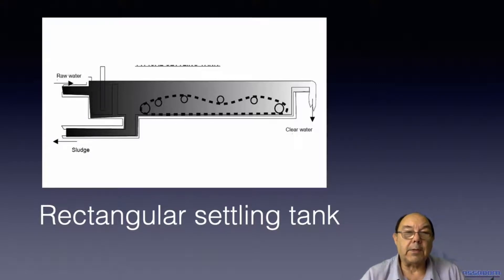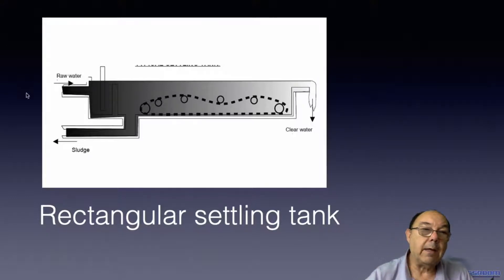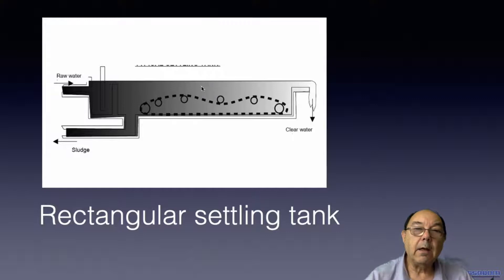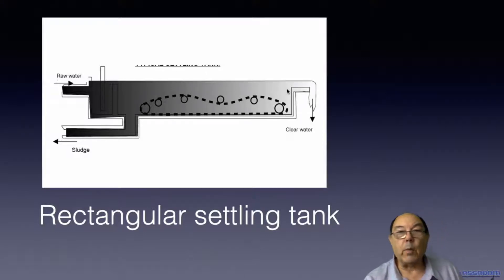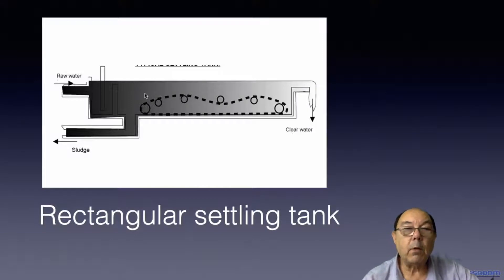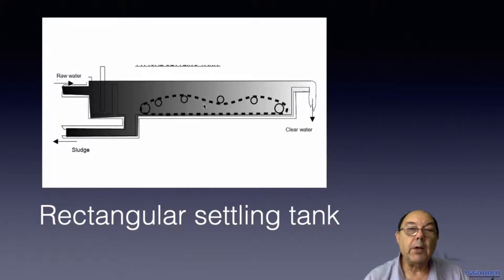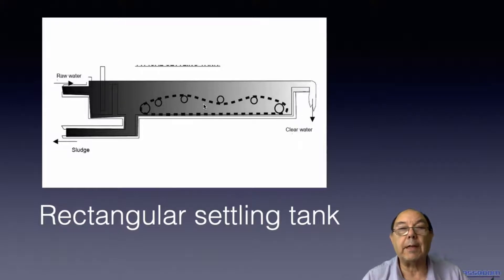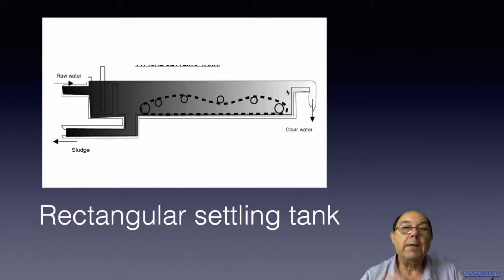This is a rectangular settling tank, and what's happening here is the raw water comes in at this end of the settling tank, it slowly moves this way until it finally gets to the weir, and clear water overflows. What's happening in this space is that the particles of dirt and debris are slowly settling out. The large particles settle first and the small particles take longer to settle — and this is Stokes law.